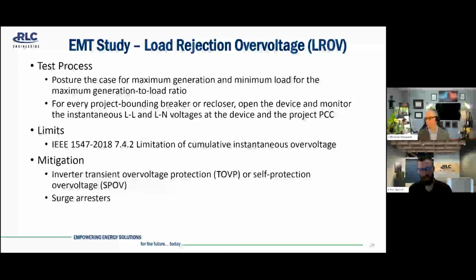So there are two components to TOV that we test. The first is load rejection overvoltage, or LROV. And this test process involves posturing the case with maximum generation and light loading, and then testing the potential island. So the limits, as I mentioned, are 1547, 7.4.2, and some tools we have in our toolbox to mitigate any violations are first, inverter transient overvoltage protection, or TOVP, or self-protection overvoltage, or SPOV. These are largely the same thing, and manufacturers may implement them in different ways. I think SPOV is actually a more popular term these days. But again, they're largely the same thing, and they're kind of the no-cost solution as they're implemented right in the inverter firmware, and don't typically require external devices. For external devices, we have the option of implementing additional surge arresters, and that's been shown to help.